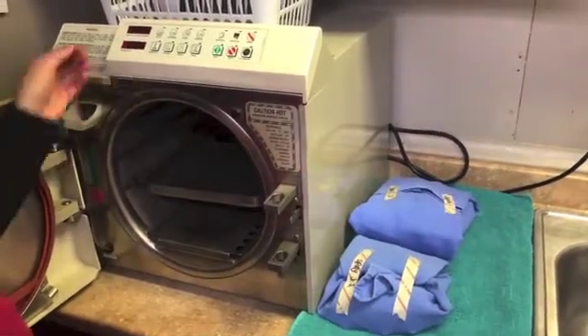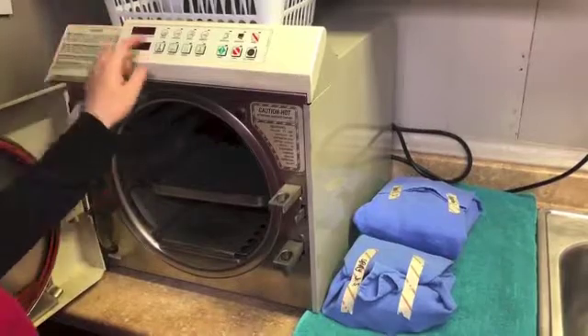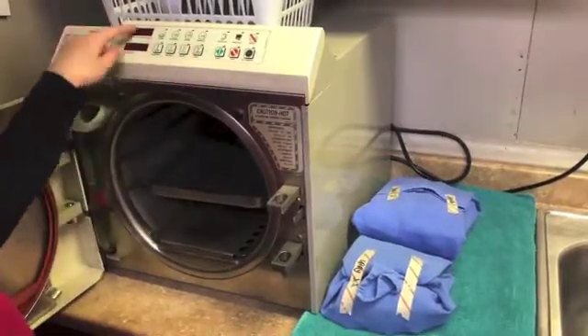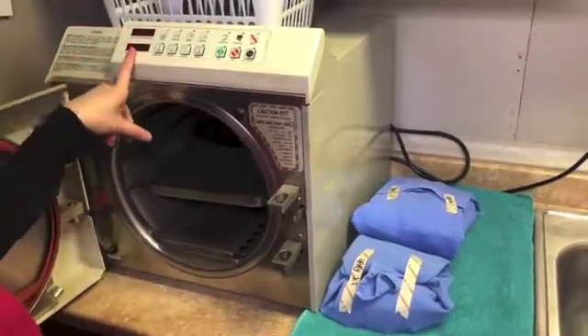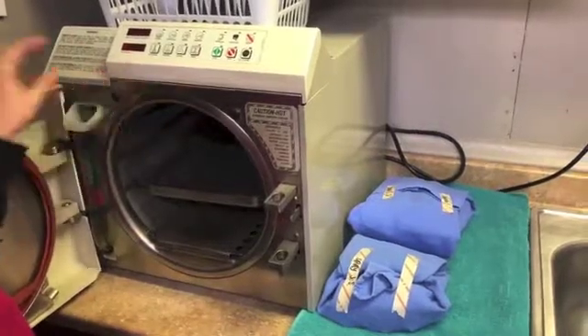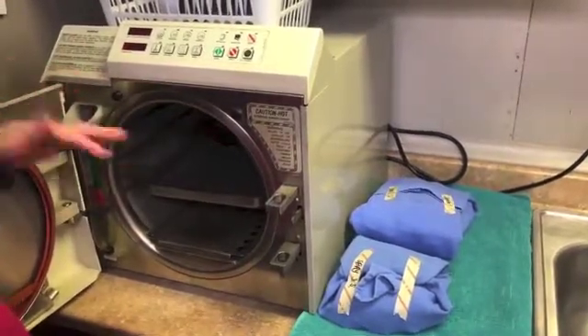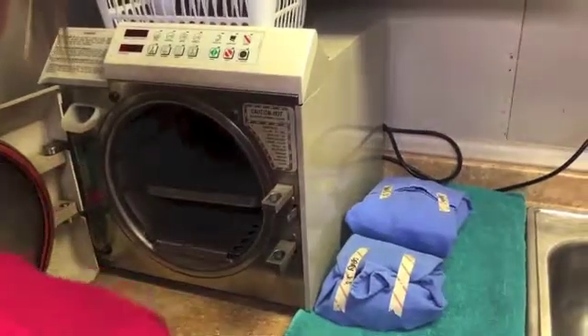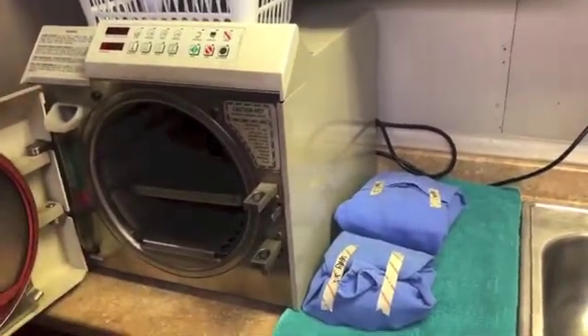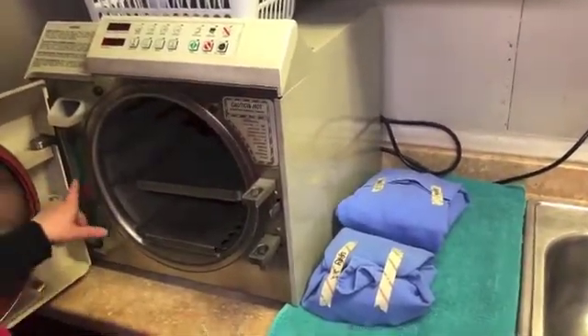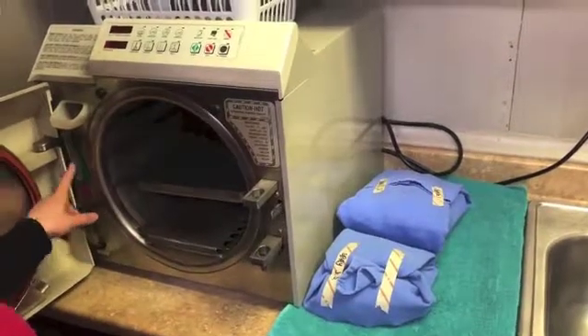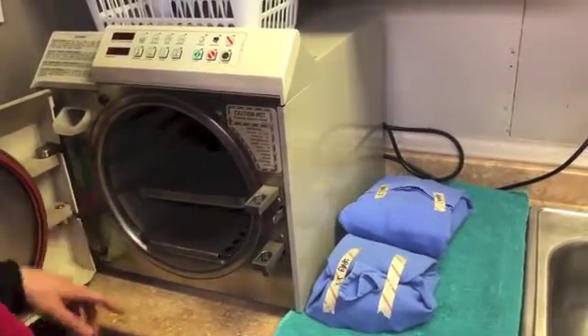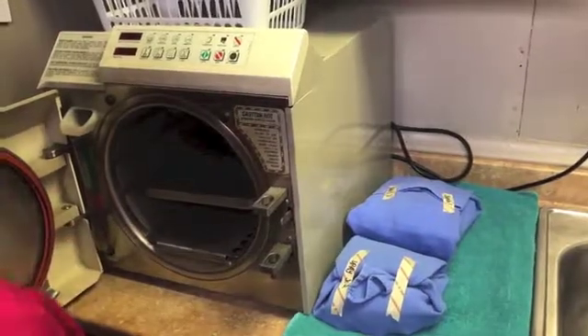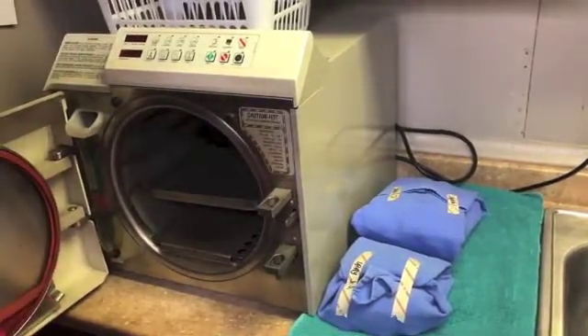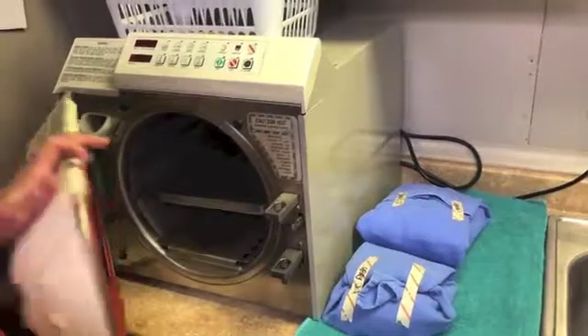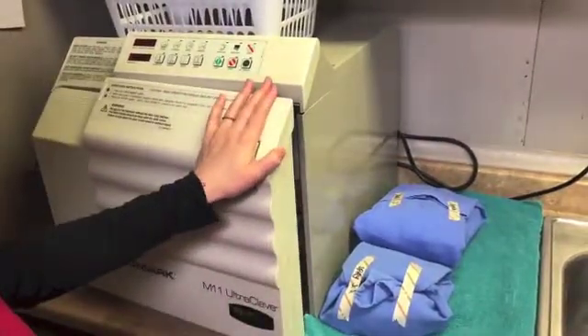So the pressure and the temperature all depend on what setting that you hit. It'll automatically set that for you. And most autoclaves come with a manual on how you're supposed to run the machine and everything. It also tells you what to do as far as maintenance goes. We always have to make sure that this is filled up to the green with distilled water. Failure to use distilled water could result in equipment damage or personal injury, is the warning that is said.